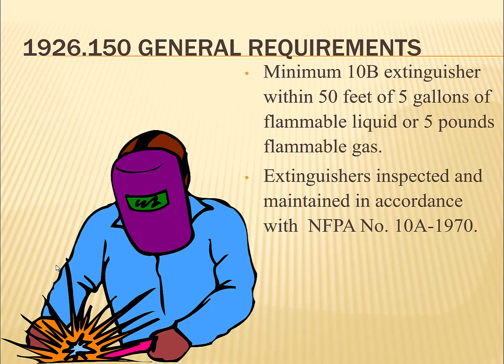And then if you're around flammable liquids or flammable gases, you have to have a fire extinguisher that is rated at least 10B. So it has to be up at that number 10 level on the rating system for how good it is at fighting a Class B fire.